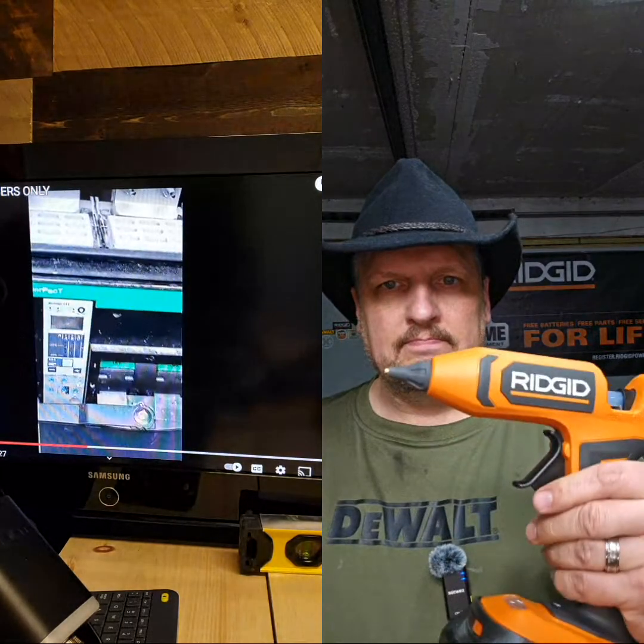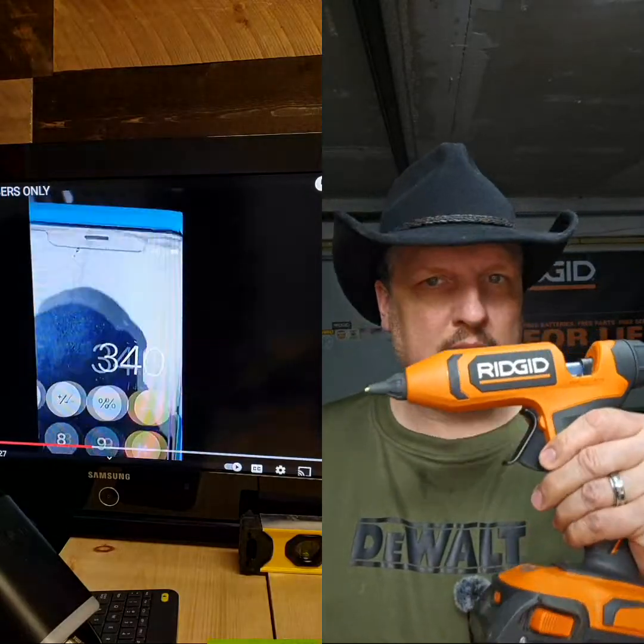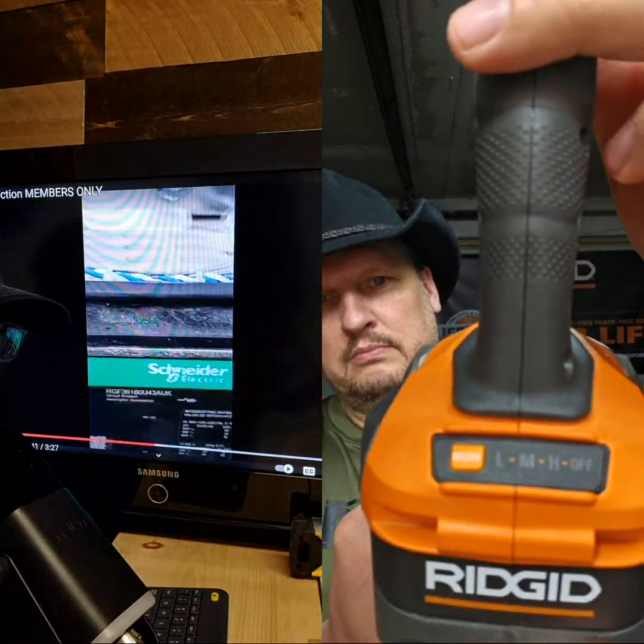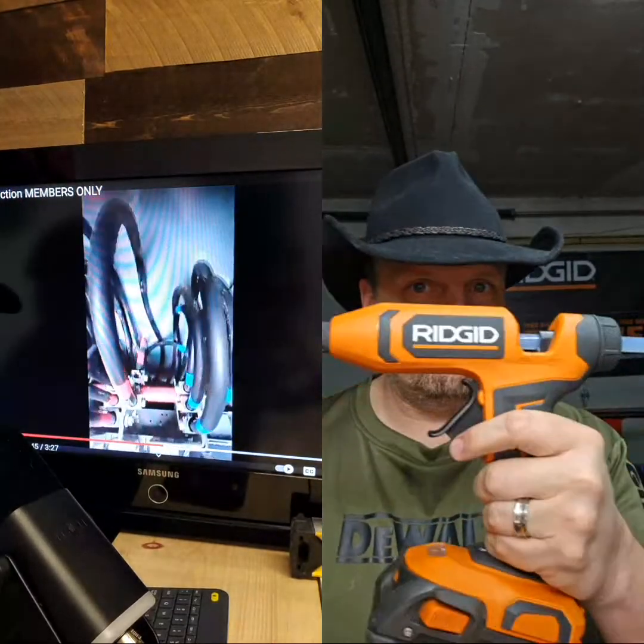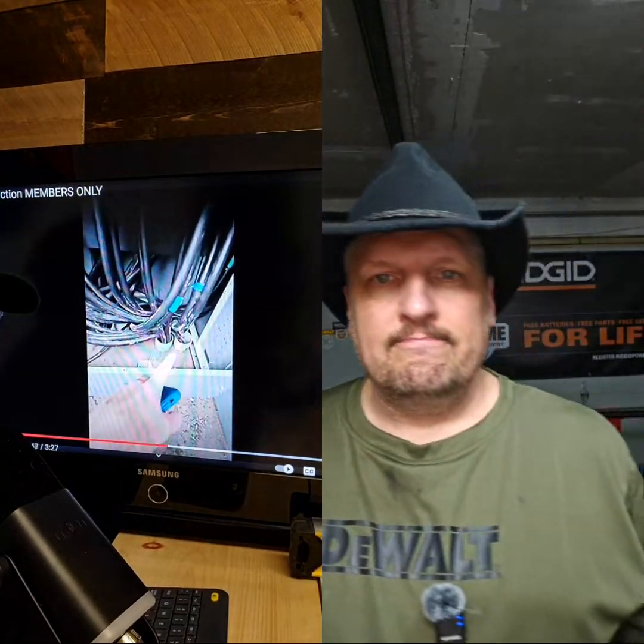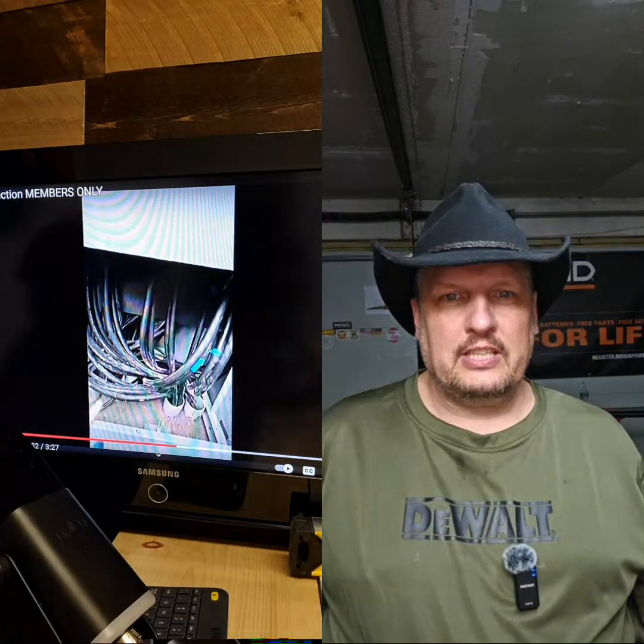Now we got to see how many sets of these in this thing. 5 times 340 is 1700, we need 1600 amps, looks like we're going to be okay. Now we got something called line and load to make sure we can fix that up. So we got to verify which conduit is line, which conduit is load, and make sure the line goes where it belongs.